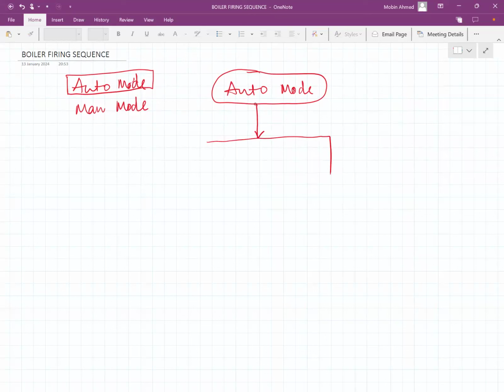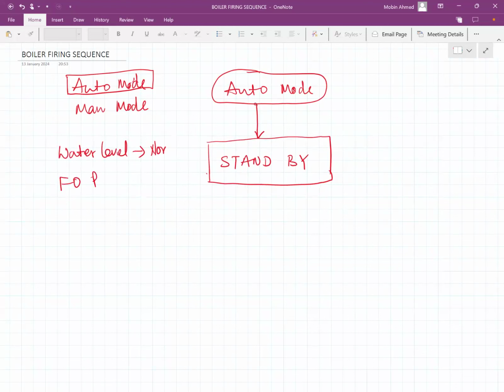In auto mode, it's supposed to be in standby. Okay, standby. When we say standby, it means it should not be in the alert or alarm position. Standby means it will come to standby if your water level is normal, then FO pressure. Okay, I will write here only. All the things below should be normal: your water level, FO pressure, FO temperature, FD fan. Once it starts, it should be running only. Or no trip. FD fan should not be in the trip. No trip.